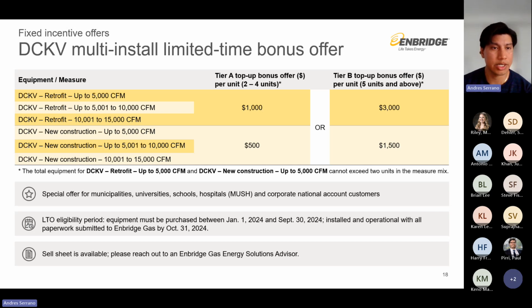As you can see from the table in front of you, we offer this for both retrofit and new construction. We have two tiers, tier A and tier B. The more units you install, the more bonus offer you receive. So in addition to the standard offering that we have for DCKVs, you will receive an additional $1,000 if you install 2 to 4 units. If you install 5 units, you will receive $3,000 in addition to the standard offering for every unit that you install. This is really great for any companies that have multiple restaurants or have franchises across Ontario. So definitely look into this if you are looking to decrease your natural gas use and looking to get some money back from Enbridge Gas.